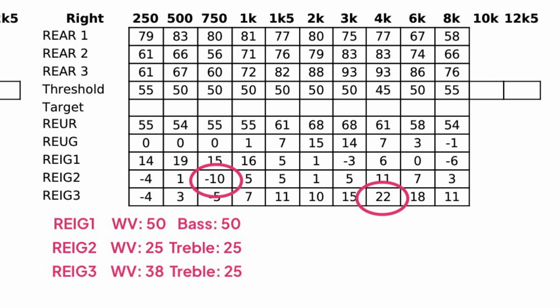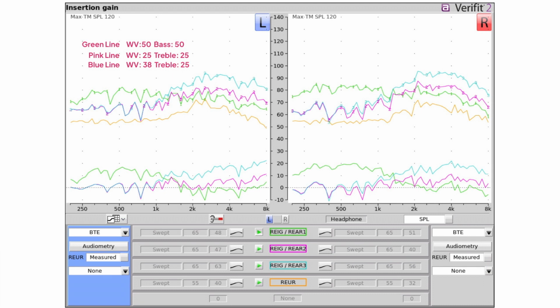Insertion gain was from -10 to 22 dB depending on the world volume and treble bass settings. The green line shows insertion gain for when the world volume and bass are both set to 50, so you see more gain in the lows and up to 19 dB of gain at 500 Hz, actually. The blue line shows insertion gain with world volume at 38 and treble set to 25, which actually amplifies greater than NAL-NL2 targets for a mild to moderate sloping hearing loss. Insertion gain reaches up to 22 dB at 4K and is negative in the lows, which is what we'd expect.